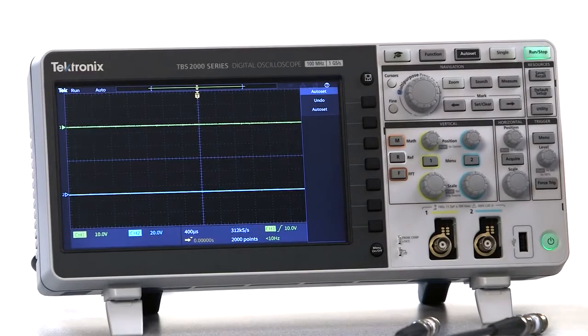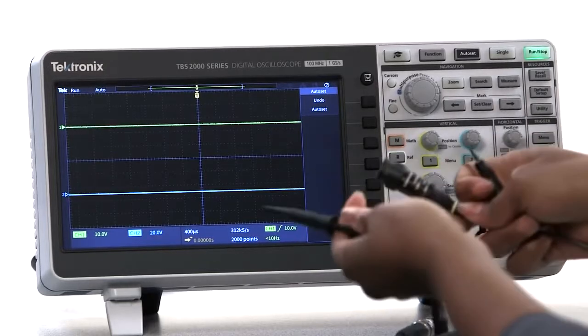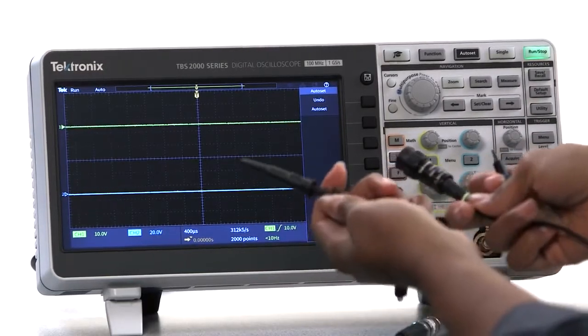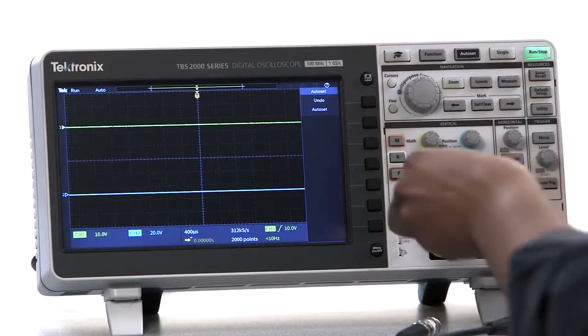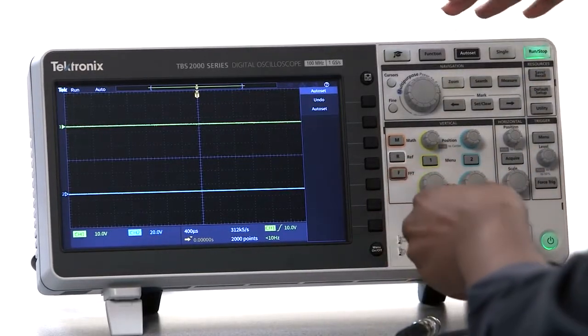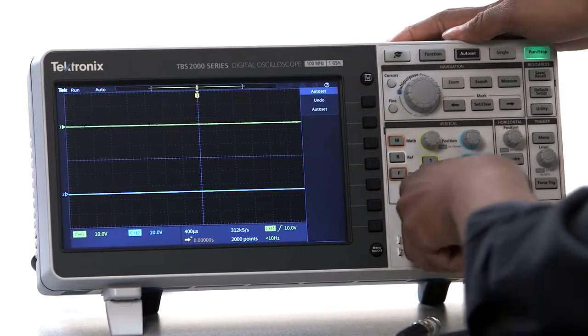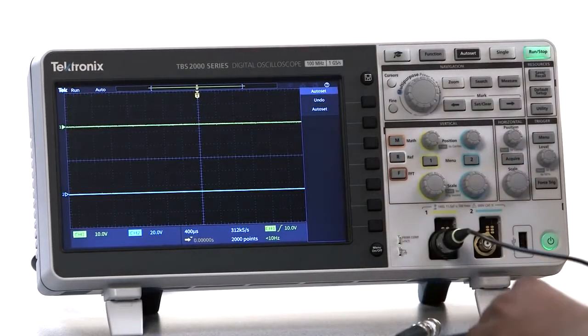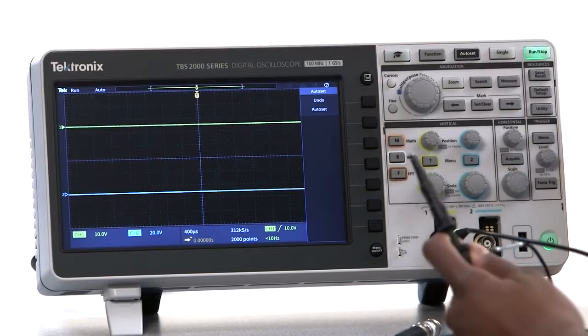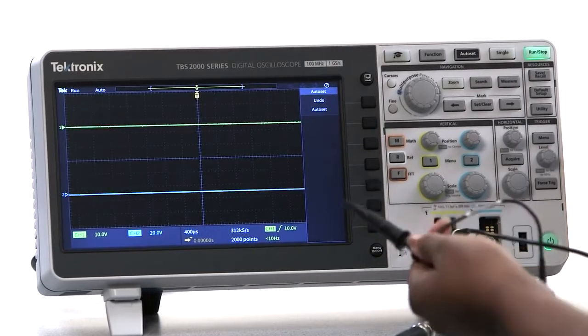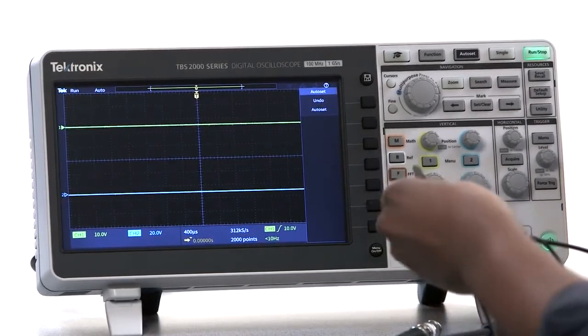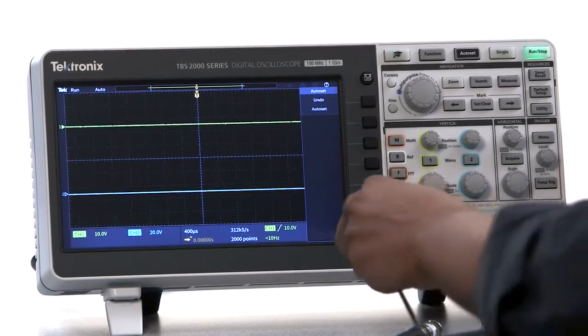Probes are often underappreciated. They're responsible for actually capturing the signal and actually impact all of what you see on the signal downstream. The most common probes divide or attenuate the input signal by 10. These are called 10x probes. They can measure relatively high frequency signals and have good voltage range. You need to adjust or compensate these probes to match the scope input. To compensate these probes, connect its inputs to the compensation output.